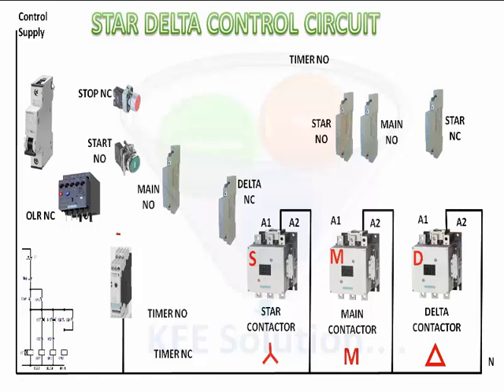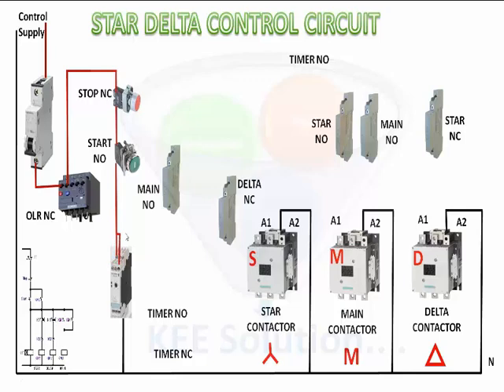Now see how the connections are made. The power will come through the MCB, then the overload relay, then it will go to NC of stop and start, then it will go to the timer and give a loop to the common of the timer.